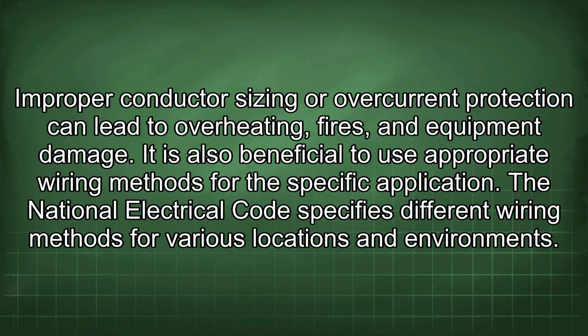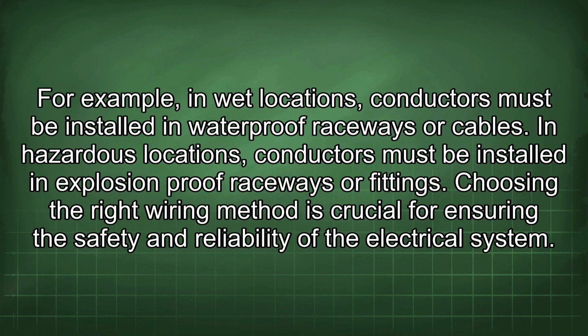It is also beneficial to use appropriate wiring methods for the specific application. The National Electrical Code specifies different wiring methods for various locations and environments. For example, in wet locations, conductors must be installed in waterproof raceways or cables. In hazardous locations, conductors must be installed in explosion-proof raceways or fittings. Choosing the right wiring method is crucial for ensuring the safety and reliability of the electrical system.